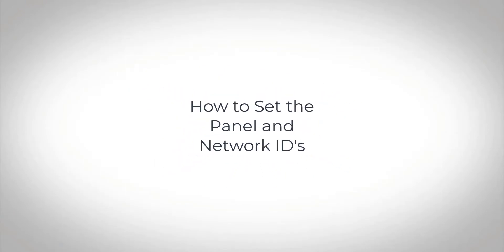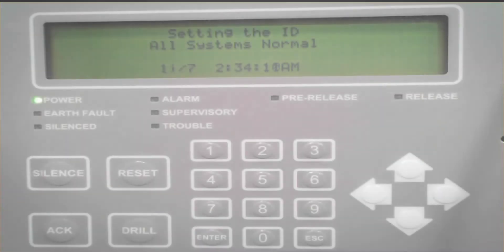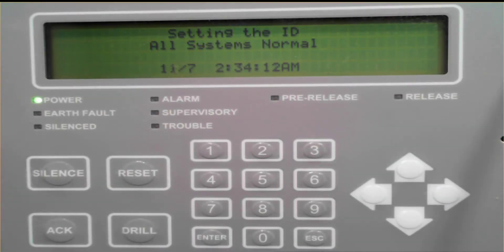Welcome to Potter's training video on how to set the network ID and panel ID on your control panels. Panel and network ID must be set before the panel will recognize the NCE and NCF-1000 network cards during a panel learn function. Whether it's for an existing network panel or a new panel, it's the same process.